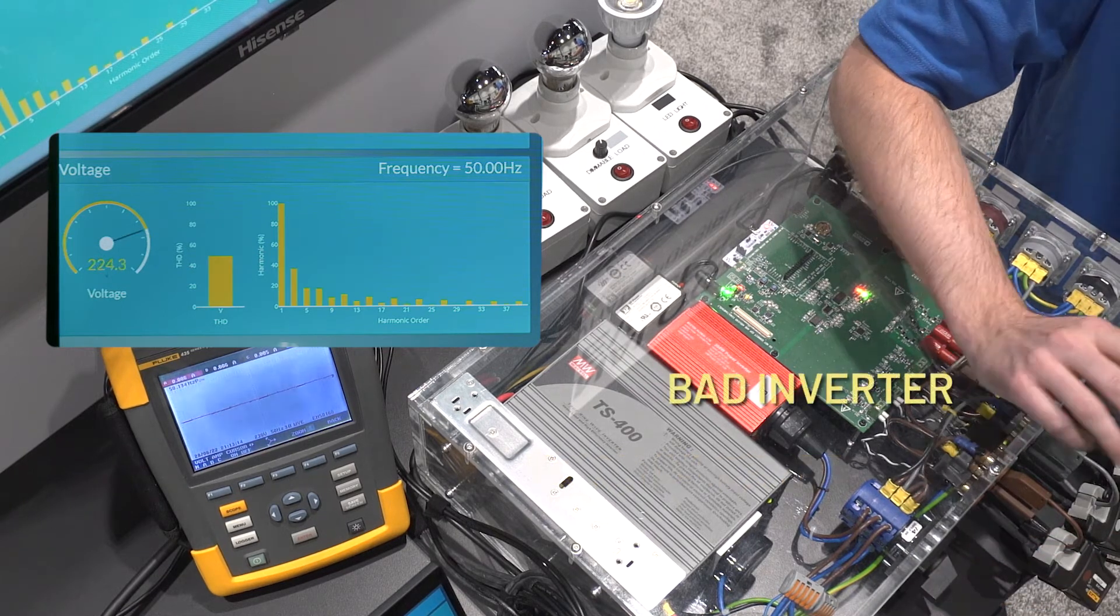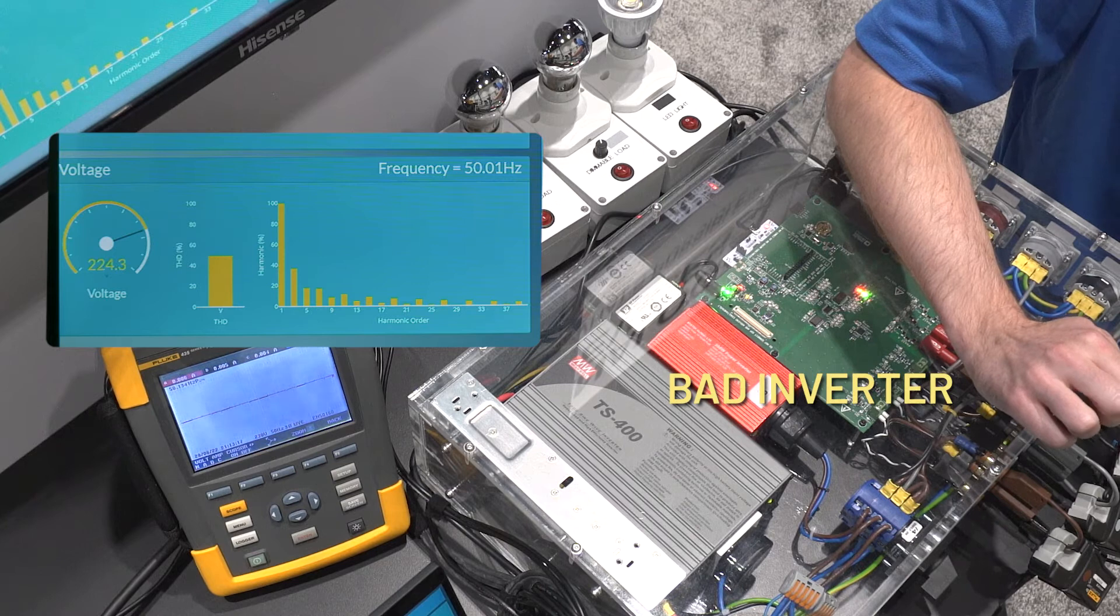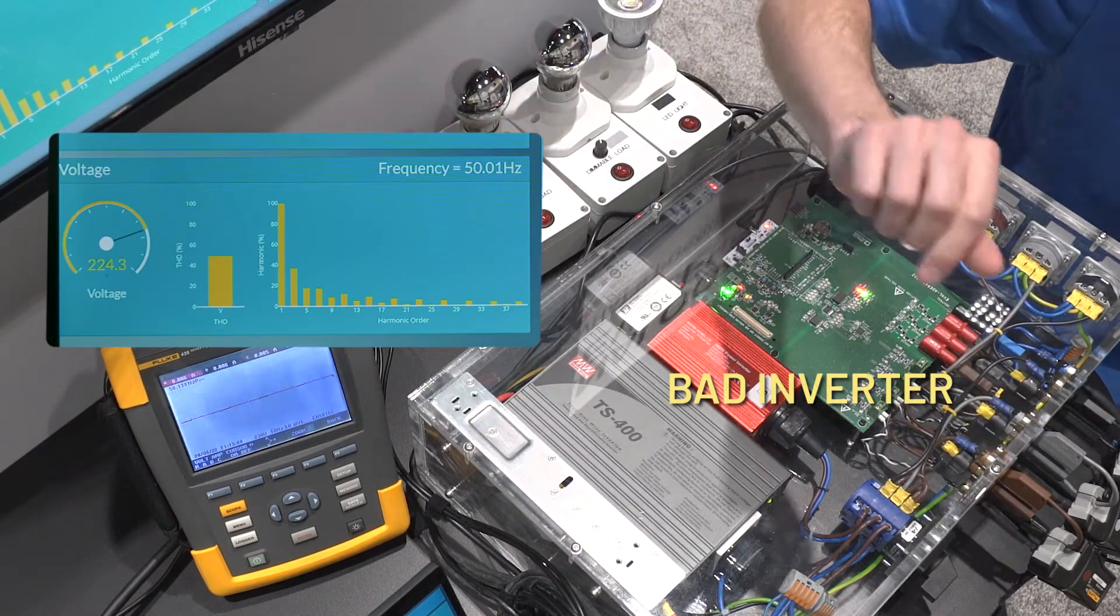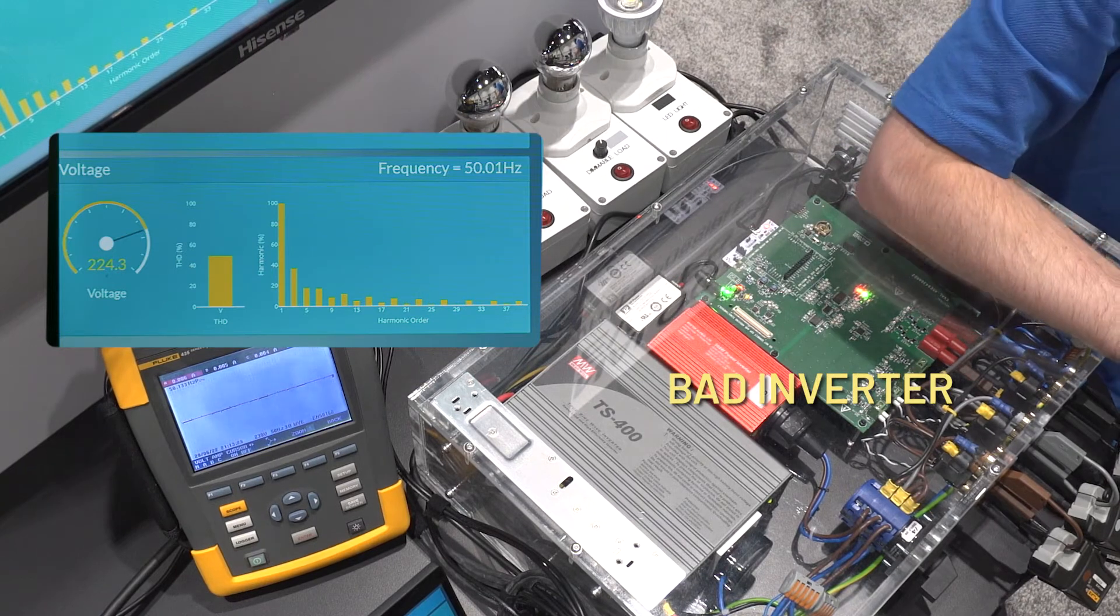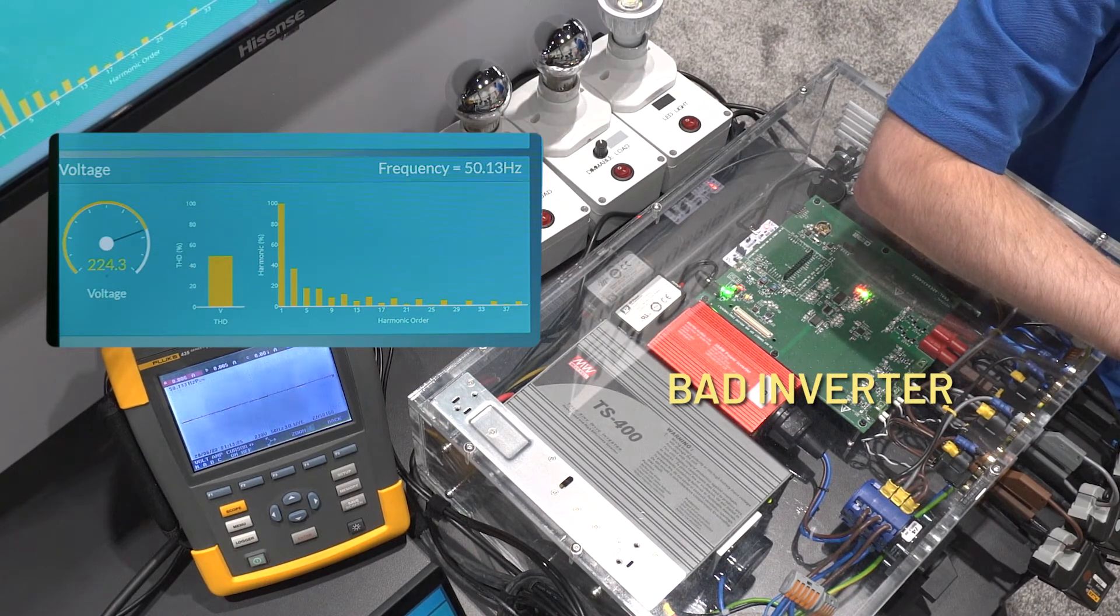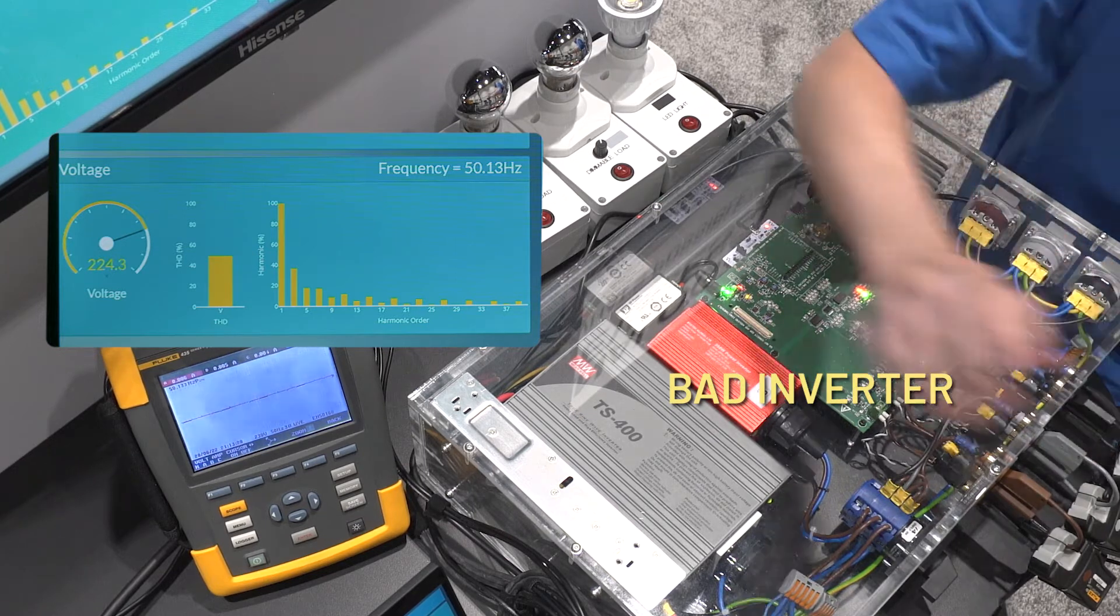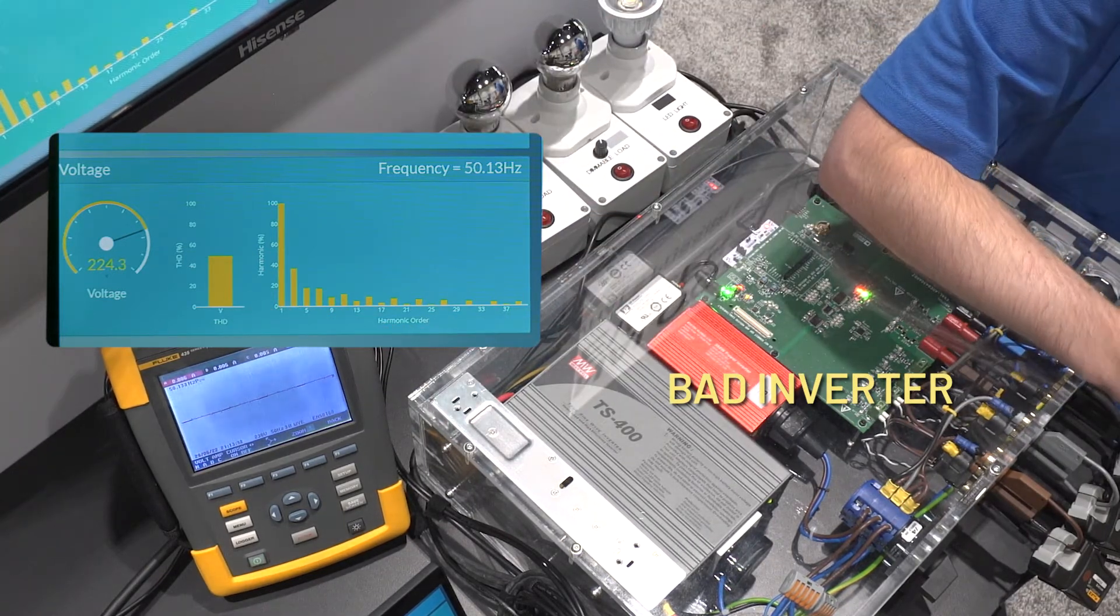The difference in performance is easily identifiable with the GUI showing the levels of THD and harmonics when we switch from the clean to the dirty signal. Multiple harmonics are increasing and the THD is now very high, potentially causing very important operational issues to the system.